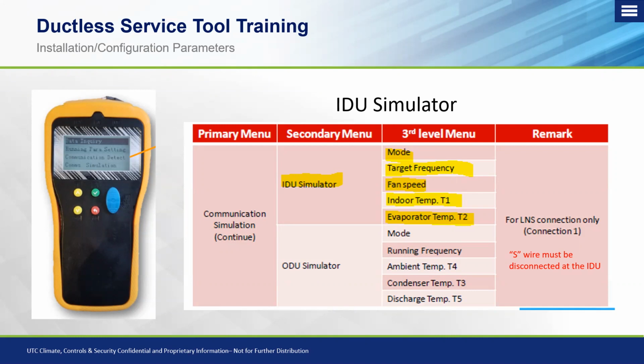Now with this, we can make changes to the mode, the target frequency, the indoor fan speed, and see an accurate T1 or T2 coil temperature. Okay. On the high wall units, the 40 MAQs, I personally wouldn't suggest doing this because they have an advanced feature that you can use the display on the unit itself to actually see those T1 and T2 values without wiring in this tool.